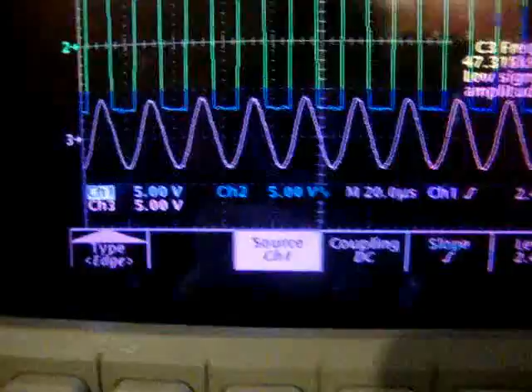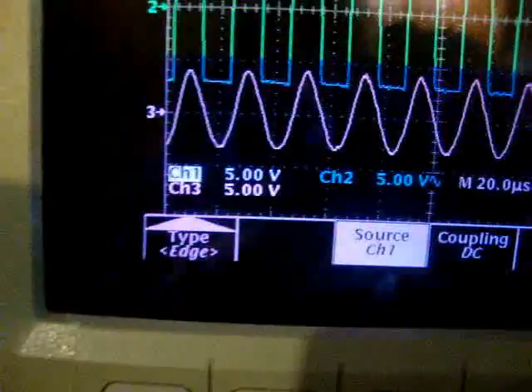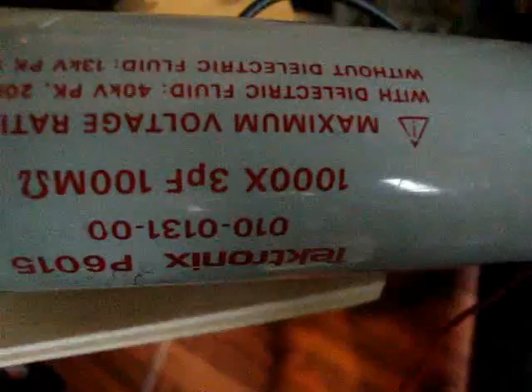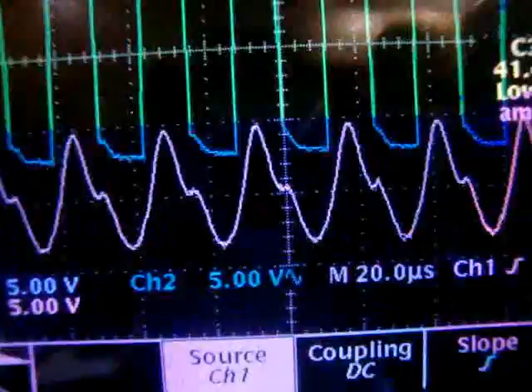Channel 3 is showing high voltage, set at 5 volts division, but the probe is rated 1 to 1000. So with a division of 5 volts showing approximately 10, that's 10,000 volts, not 12,000 volts.